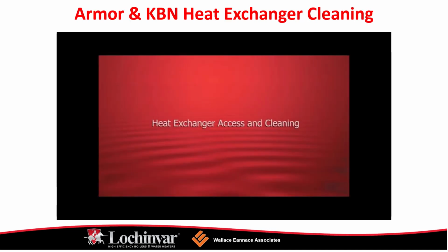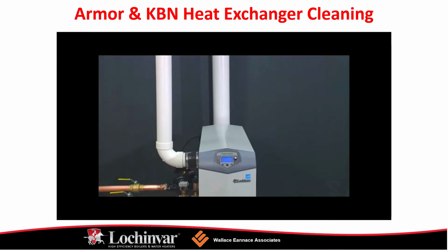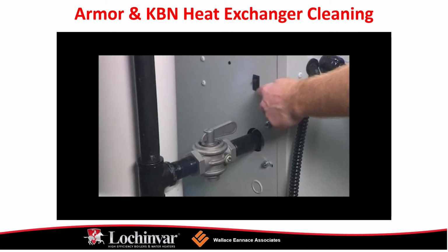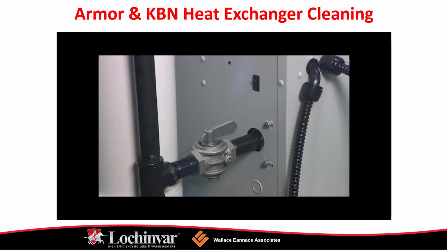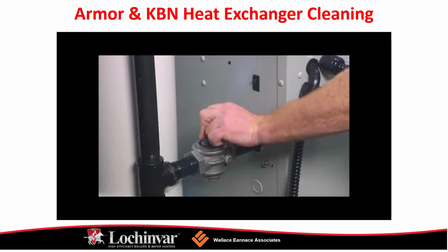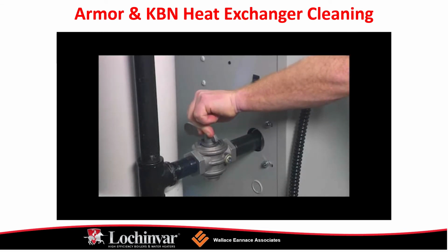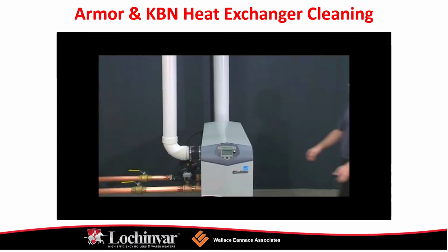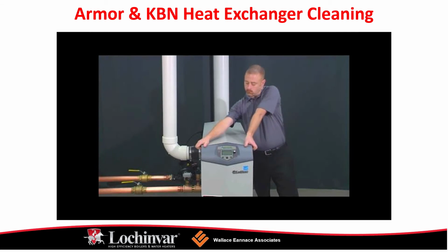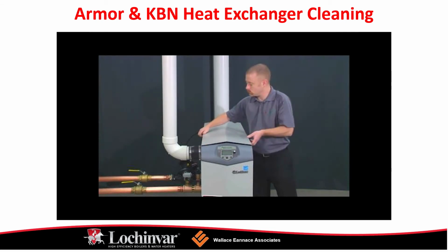The unit will fire at its normal ignition speed and will then modulate its firing rate to 100%. During service mode, the control will ignore all other heat demands. However, all safeties and maximum set point temperatures will be active. So if no other buttons are pushed, the control will automatically revert back to its original state after the service mode delay has expired. The default time for service mode delay is 10 minutes.